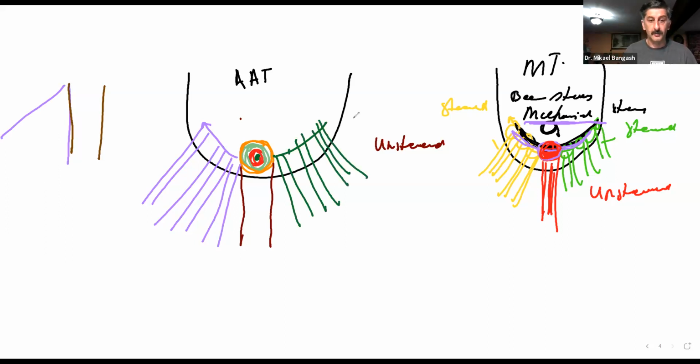So this will be steered. But mainly, the steering of your beam is going to happen by the physical movement of the bigger group of PZTs moving back and forth, or you can say right to left, right to left, right to left.